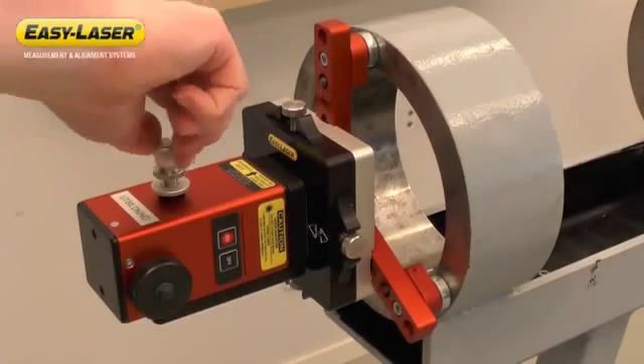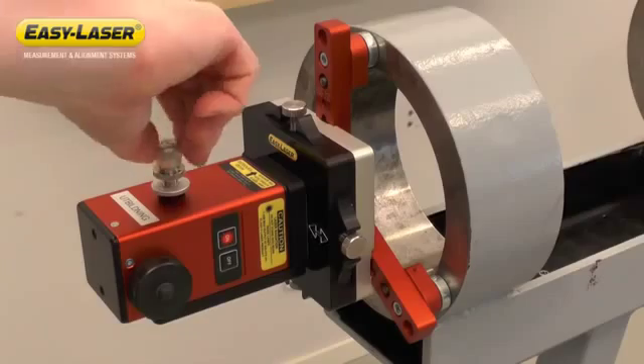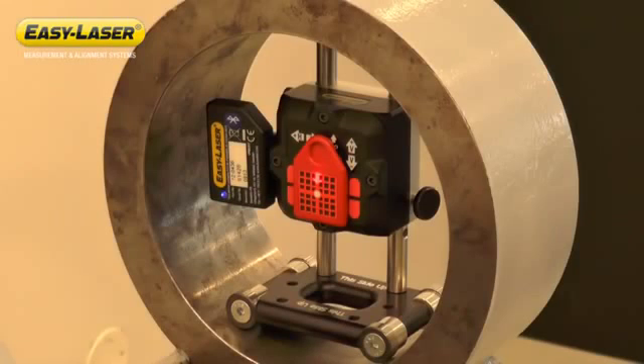First I have to align the laser beam along the measurement. I do this through adjustment of the tilt table while looking at the target on the detector placed in the bearing journal the farthest away.